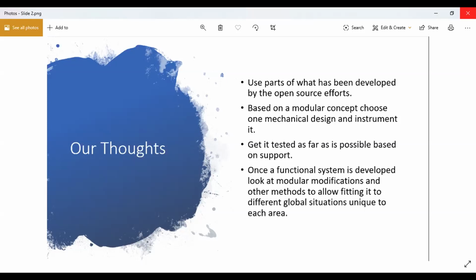Got it. But just so I understand, and Rob, I know you're going to provide more details on this: are you going to use the Israeli ambu vent design for all the physical components of that and focus on the instrumentation and code? Is that what you're doing? Yeah, basically, since we have an ambu bag, the simplest way forward was just to use that. But it depends on how you instrument it and how you activate it and how you respond to what it does when you activate it. A piston obviously is a lot easier to do volumetric control on, but we started with the ambu bag.